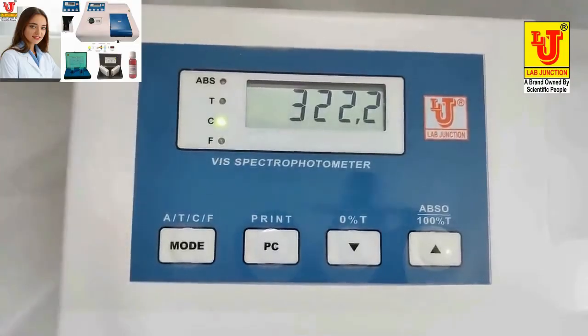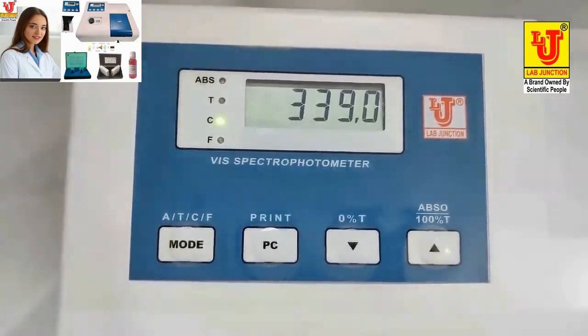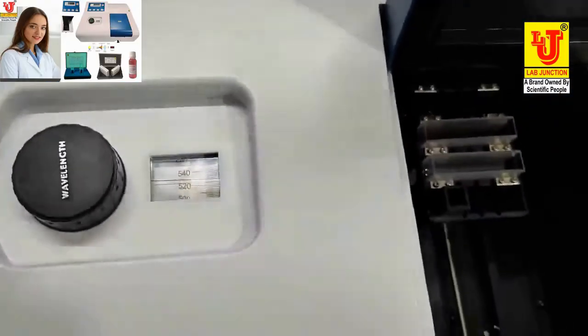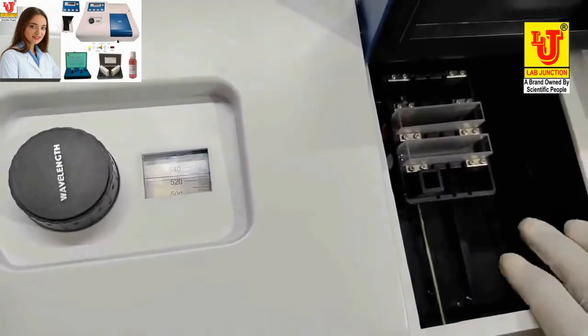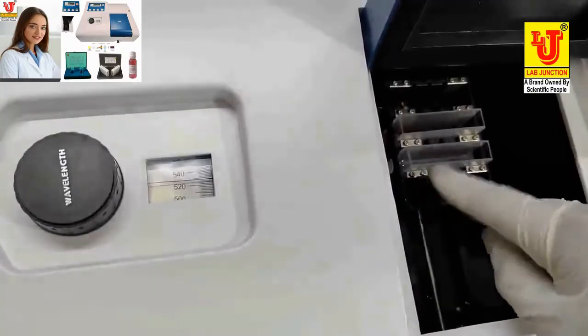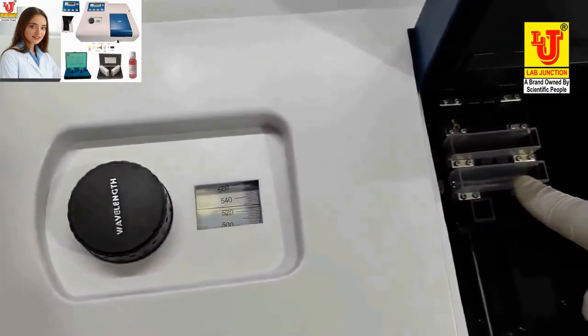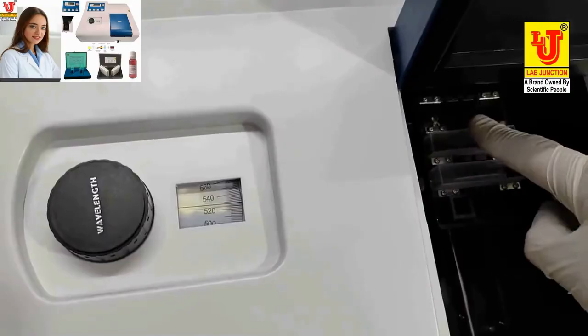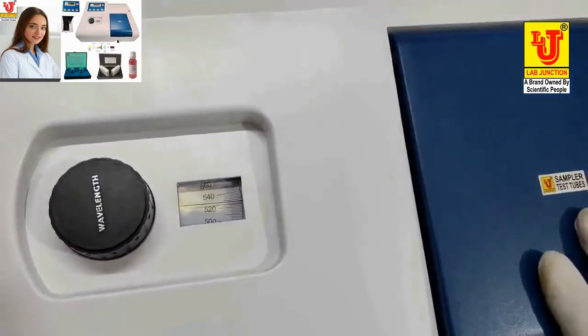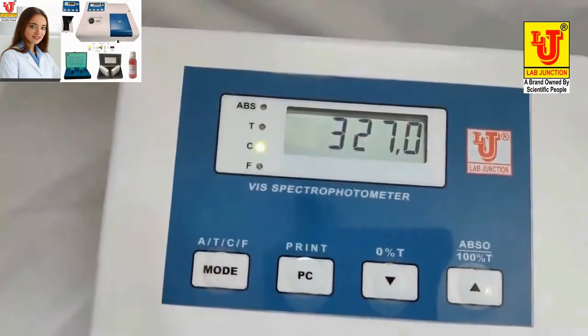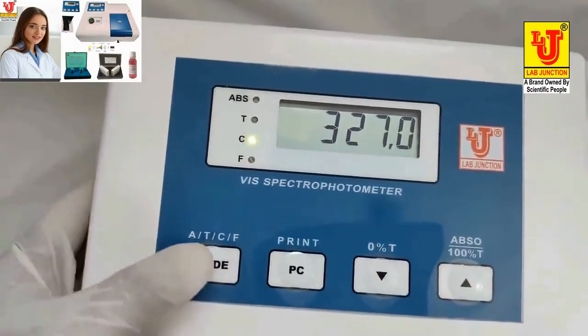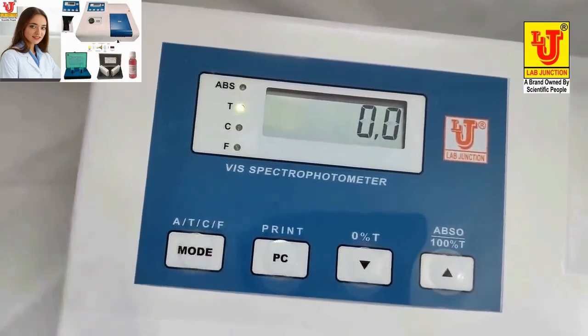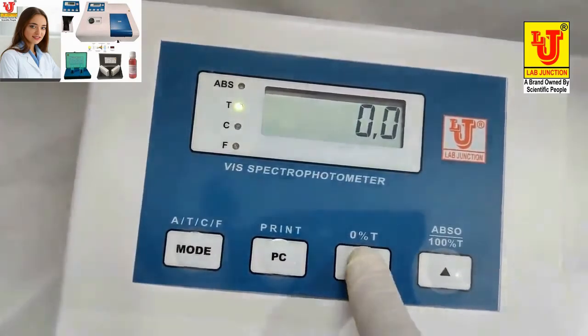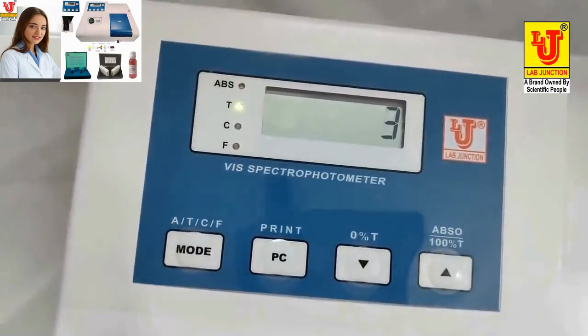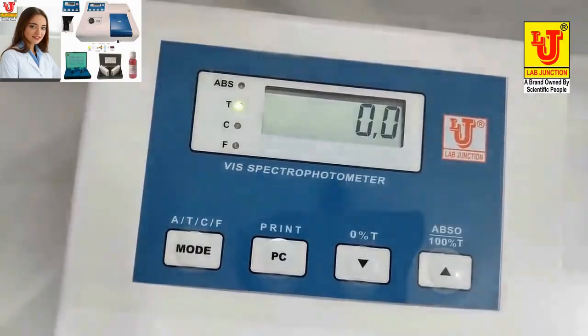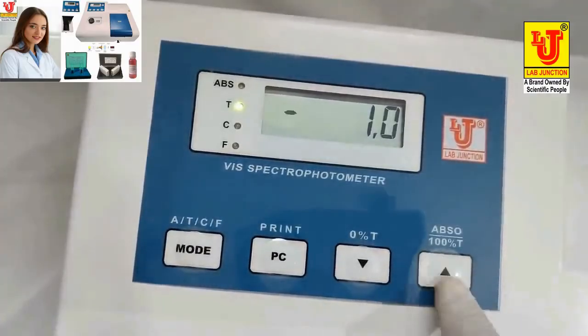You find concentration values in concentration mode automatically. Only feed the factor value in the spectrophotometer. Again I am describing. This is the dummy. First position blank, second position sample. Now first go to transmission mode. Press 0% T for preset 0. Now press 100% transmission.